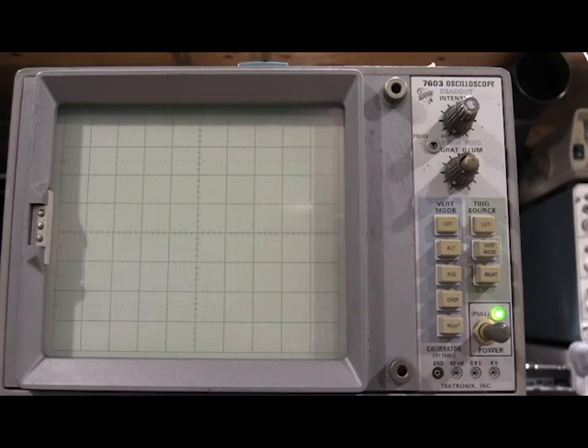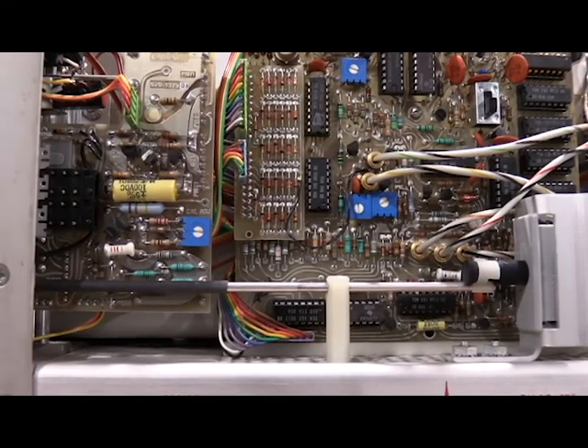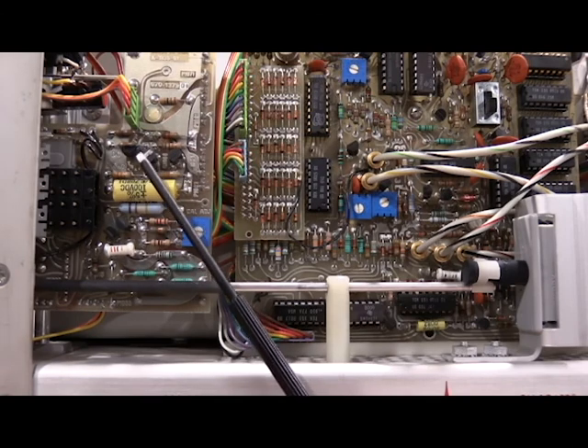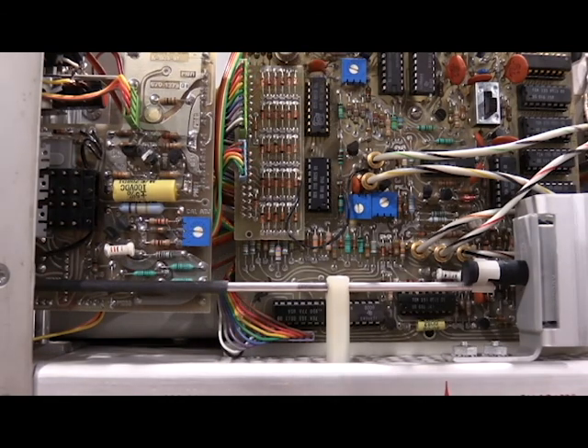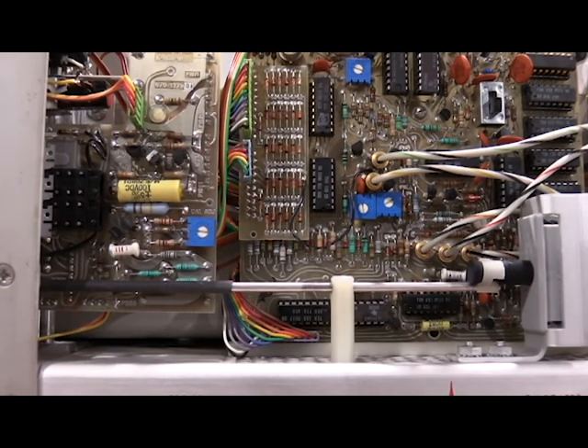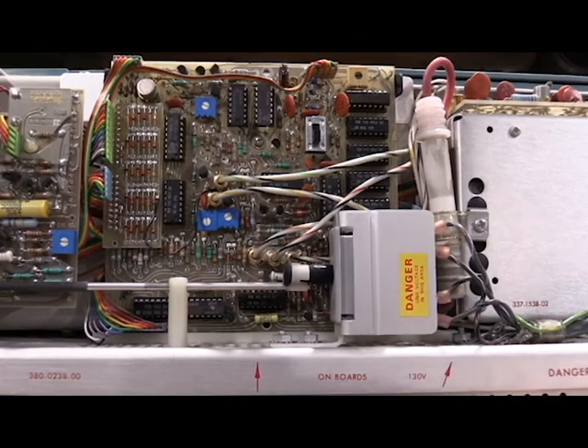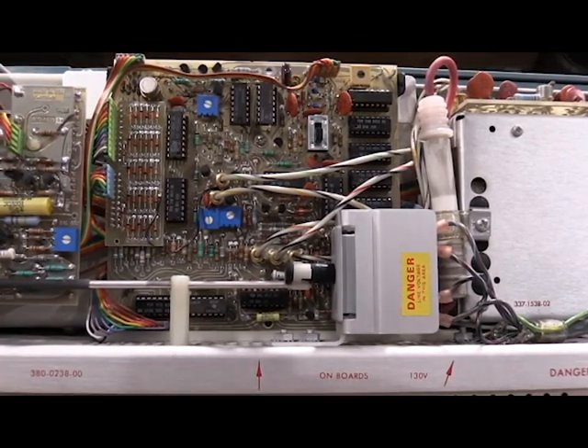So next up is adjusting the calibrator for the probe compensation. Not much to see for the calibrator adjustment. This potentiometer is adjusted for cal. You move this jumper to DC, and then on the front panel you use a DC voltmeter. I was able to adjust it to 4.001 volts, so well within spec. So it looks like it's healthy. I also checked the 0.4 and 40 millivolt calibrator outputs, and they are squared away as well. So everything looks ready to go.